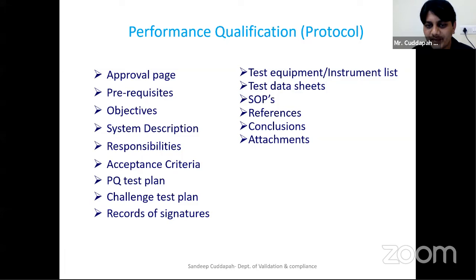In the case of performance, you will measure the rotations, whether they are as per your set point. If you have given around 50 rotations per minute as a set point to the motor, you will use a testing equipment called a tachometer, and with the tachometer you will measure whether the output is the same as your set point or not. That will be verified during performance qualification.